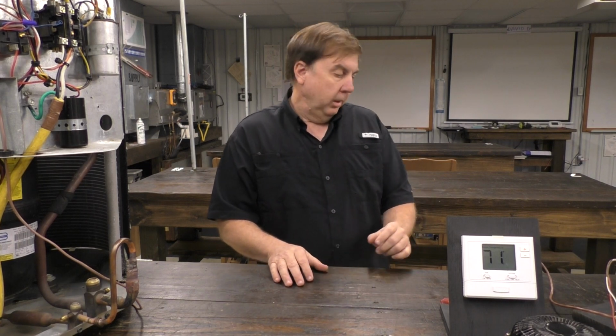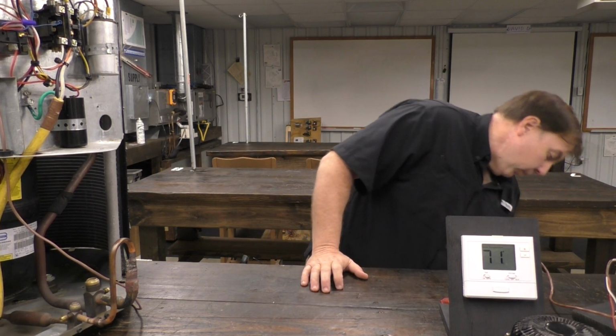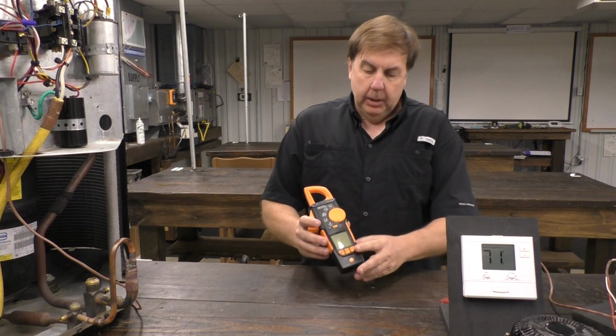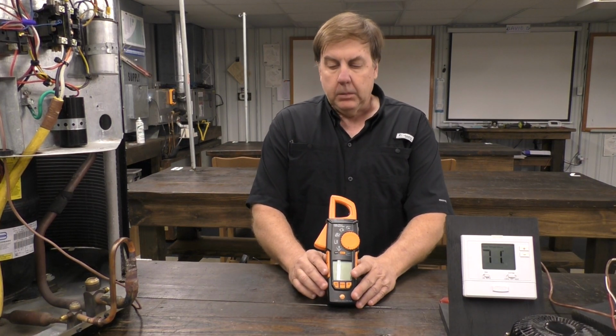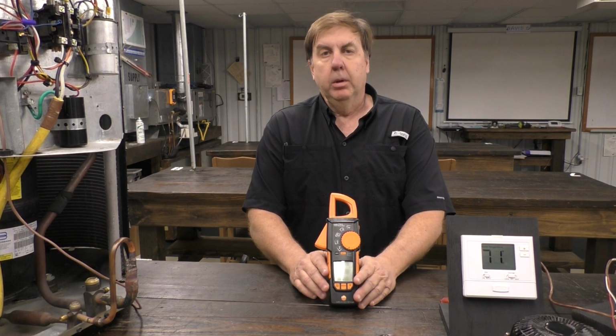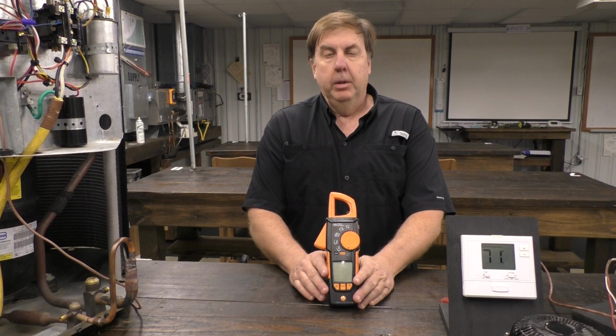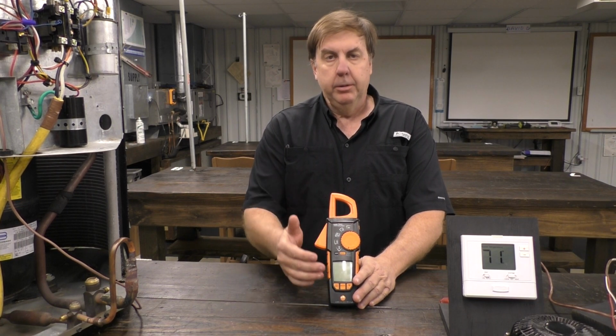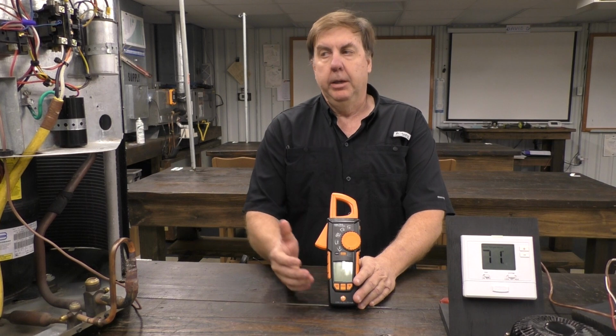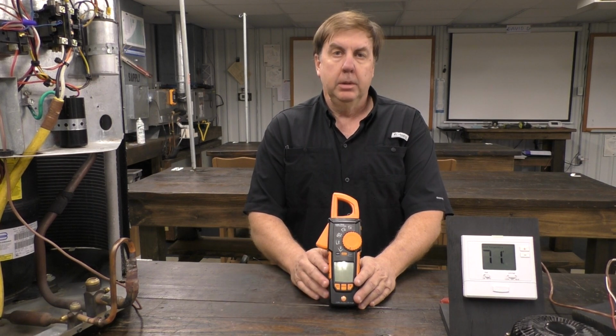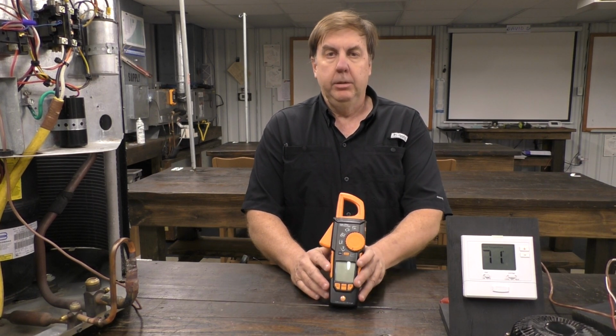You're going to be wanting to check that voltage, and you're going to want to check it with a meter so that you know if you actually did turn off the right breaker. We're going to get a meter out, just a common volt-ohm meter. But how do I know the meter works? The meter's been riding around in my truck. The display might turn on when I go to use it, it might check, it might tell me 0 voltage. Well, that's not good enough. I need to verify that.